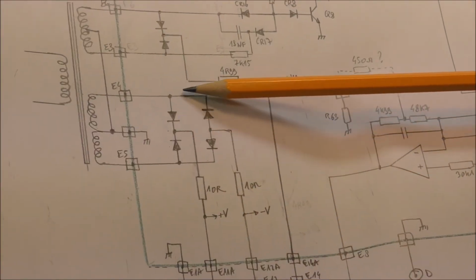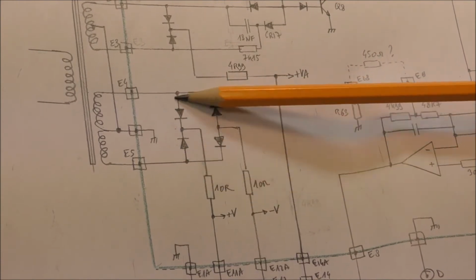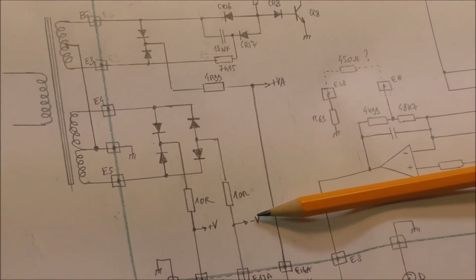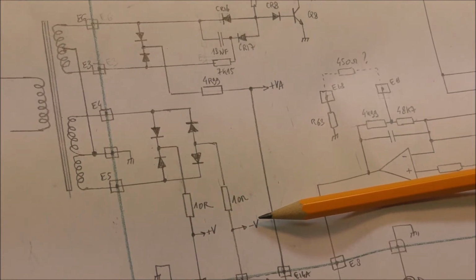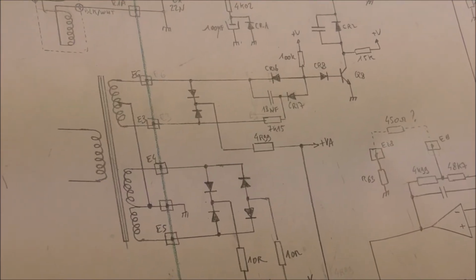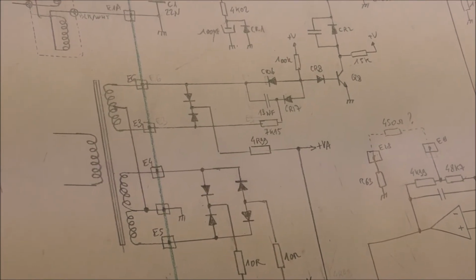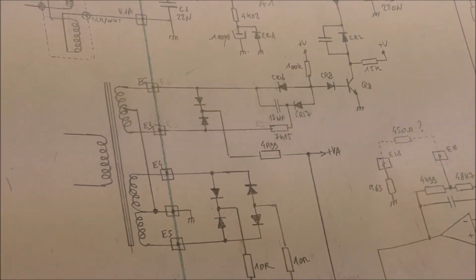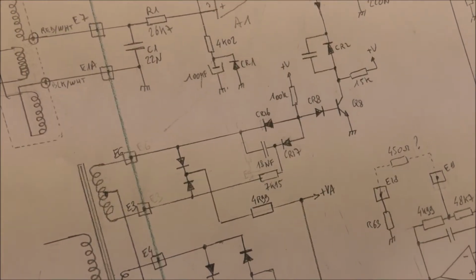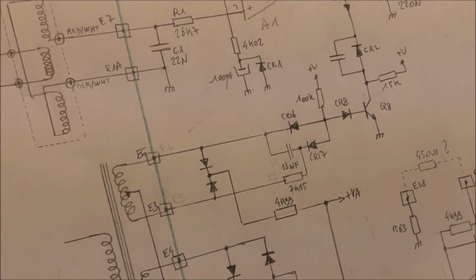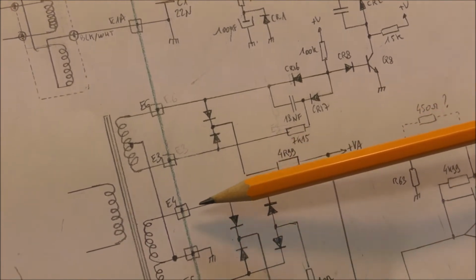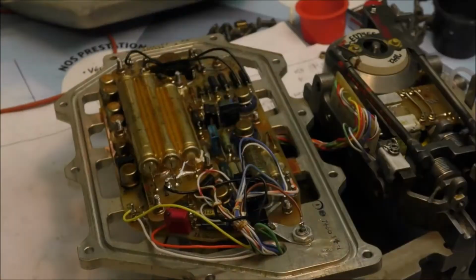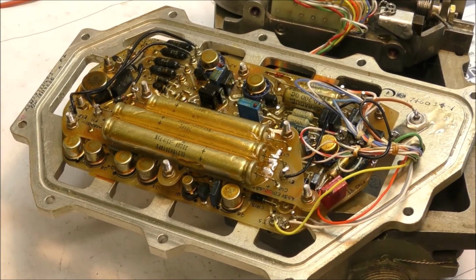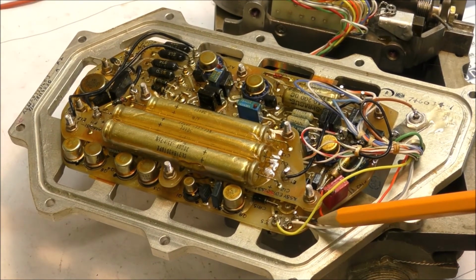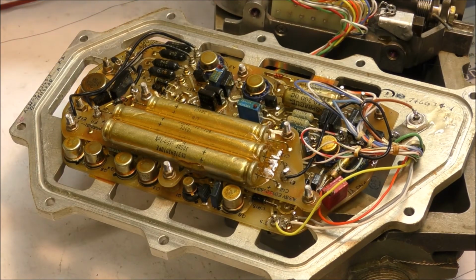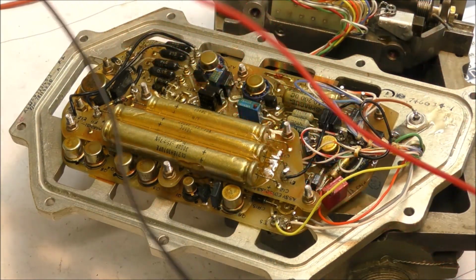I will adjust the voltage between these 2 terminals in order to have something close to plus or minus 12 or 15 maximum, and then I will try to find a voltage of 115 volts or close to this voltage between 2 pins on the rear connector. So I will connect the AC voltage between the terminal E4 and E5. E5 corresponds to the yellow wire here, and E4 the gray one. So I have prepared the power supply, an AC power supply here.